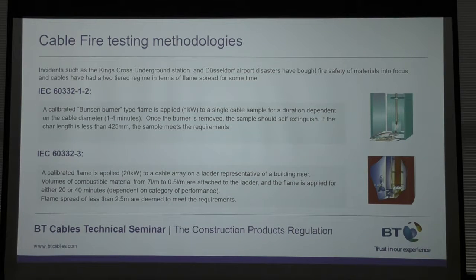IEC 60332 part 3 is the cable ladder test, which is meant to represent a building riser. The dominant test in that is 1.5 litres of combustible material per metre of ladder. Then basically you put a 20 kilowatt burner on that for 20 minutes and see how far the flame burns up.